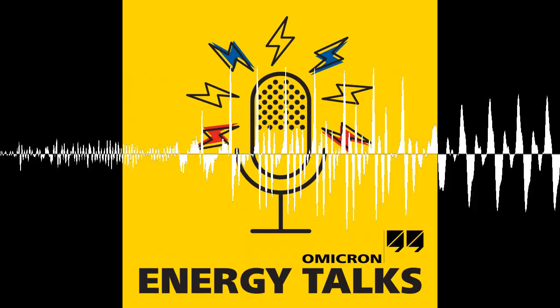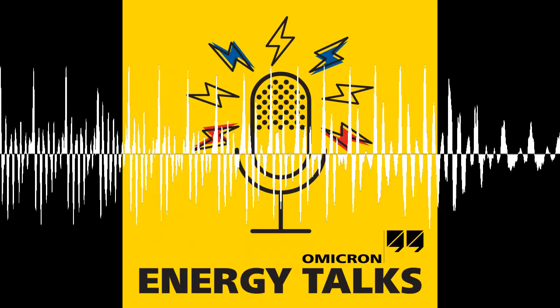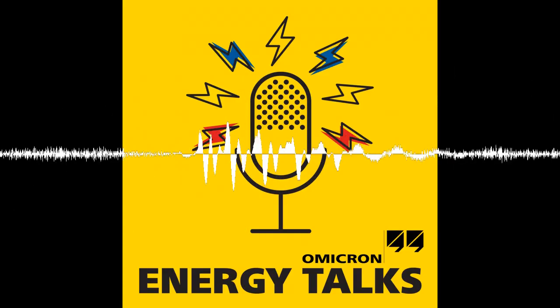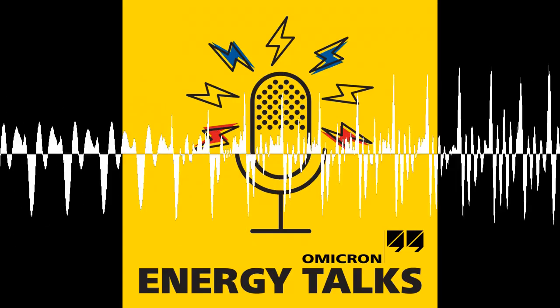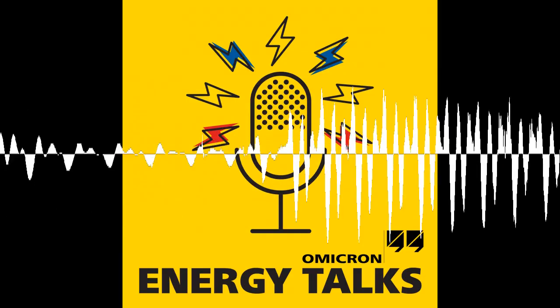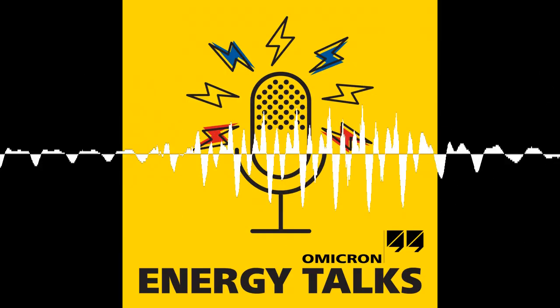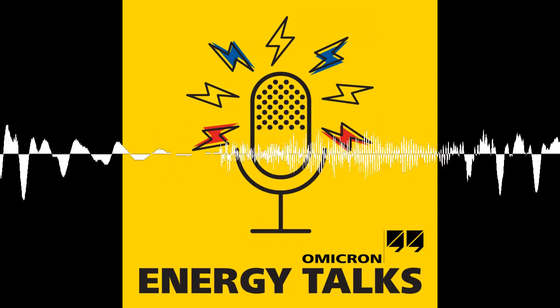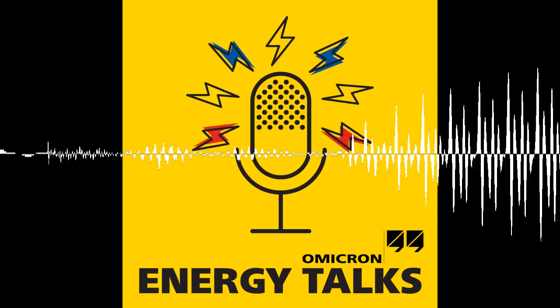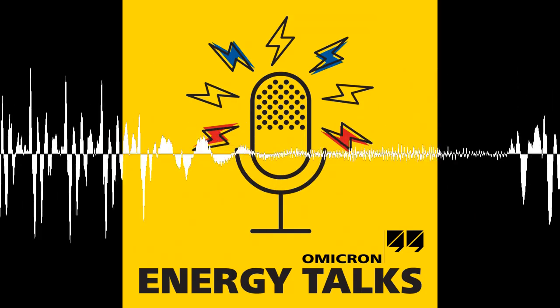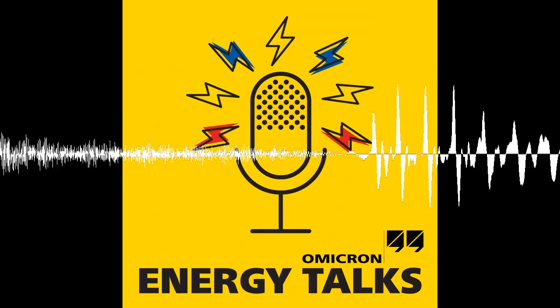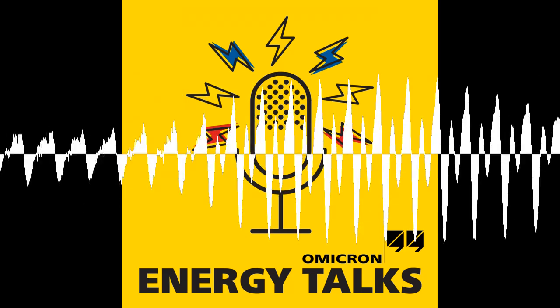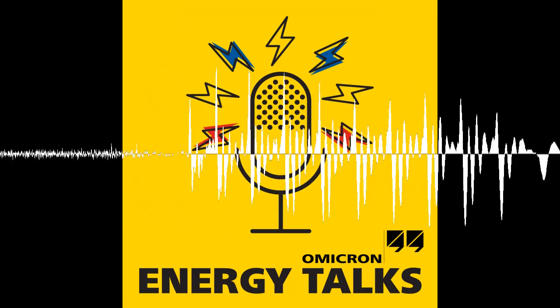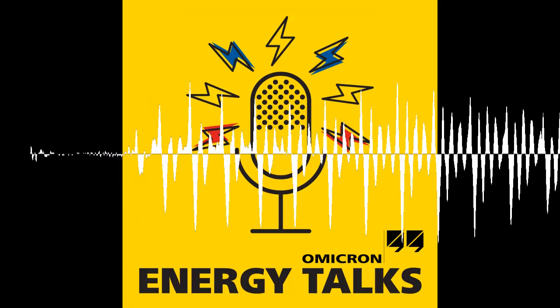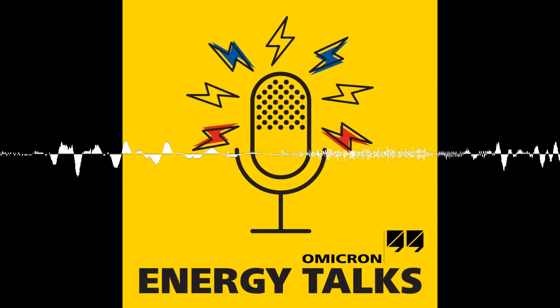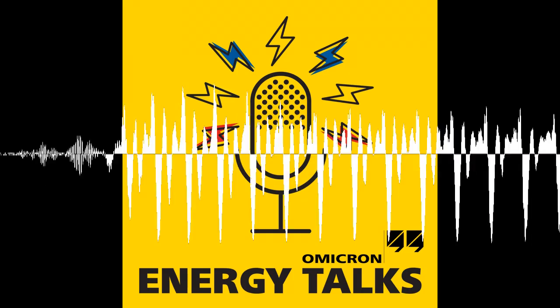Yeah. Computers have become more capable over the years and have allowed us to do even more intensive signal processing and get better accuracy, get nicer looking, better resolution visualizations, get faster ways to report, and basically have a better way to reproduce these measurements over time. And also using desktop and laptop computers, which people are familiar with, makes it easy to use something that you already know, and at the same time, using those to connect to the measurement device using a fiber optical connection makes it a lot safer to operate the device, because you don't have to be in the high voltage area. You can be somewhere where it's safe to be during the measurement.